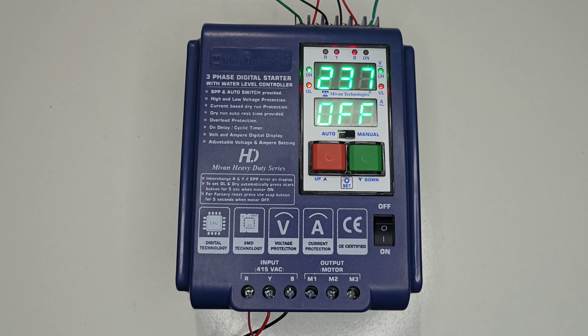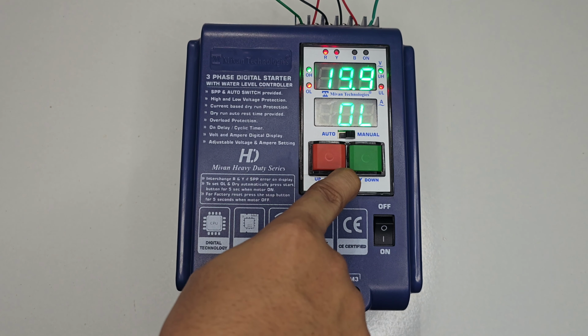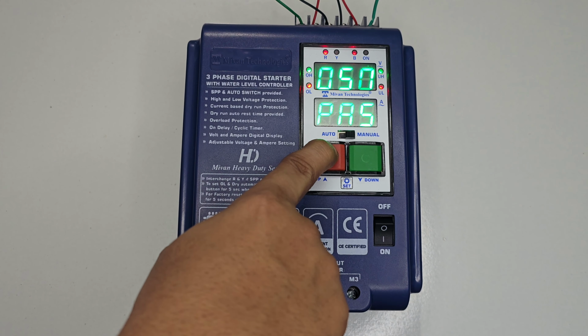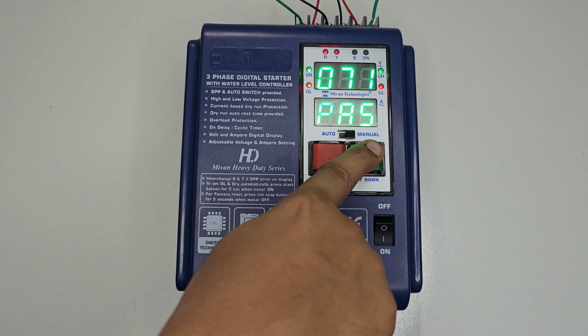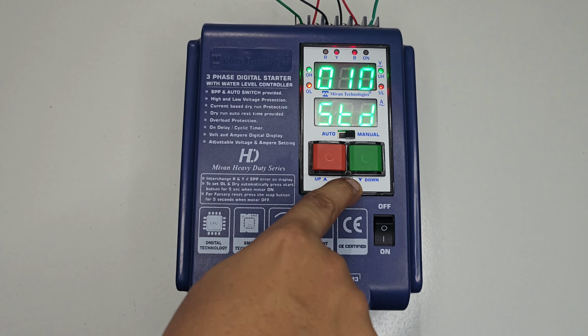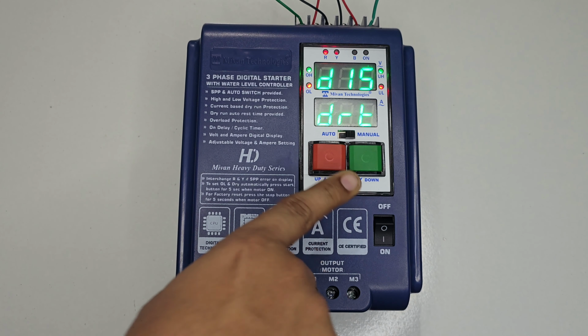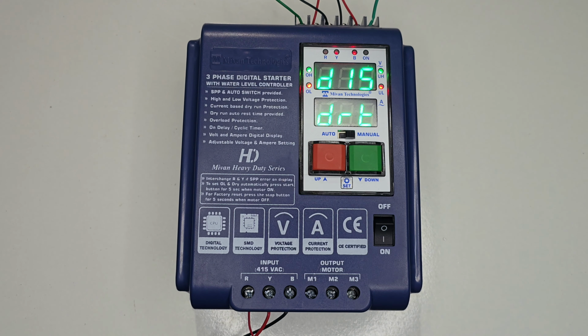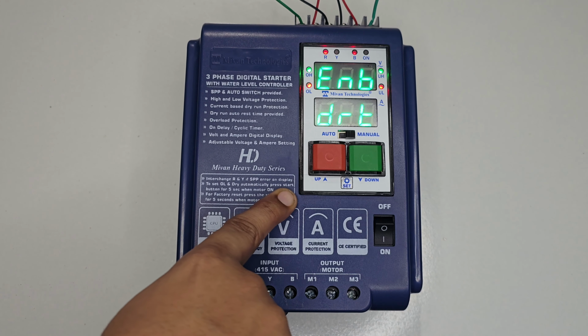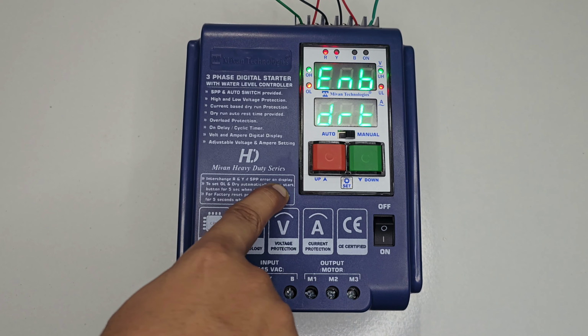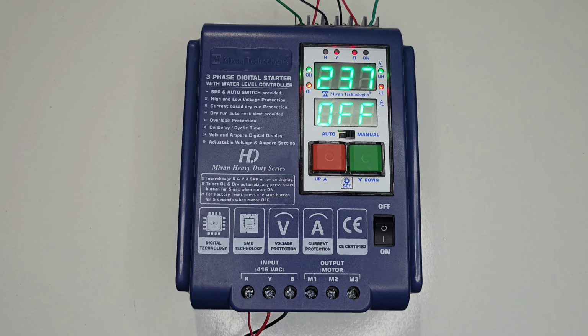Now I'll show you how to set the dry run reset timer. To set the dry run reset timer, first you need to enable the dry run reset timing option from the password 70. Press the set button for 5 seconds. You will be asked for the password. Go to the password 70. Press the set button several times. Here you can see a dry enable disable option. By pressing the up key, make dry reset enable. Press the set button, and it comes to the main menu.